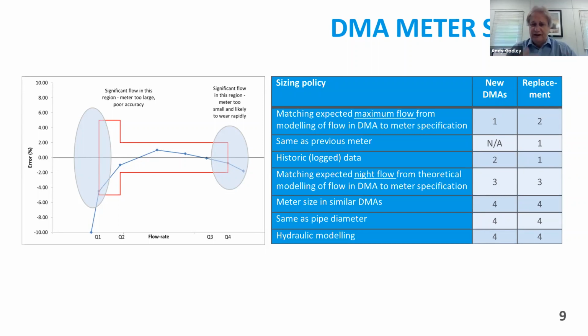So it's very important that as the DMA changes, the size of the meter is reviewed. As the nature of the DMA, the flows in the DMA and the properties in the DMA change, you keep an eye on the size of the meter supplying that DMA, to make sure that the flows are still in an appropriate regime with respect to the meter.